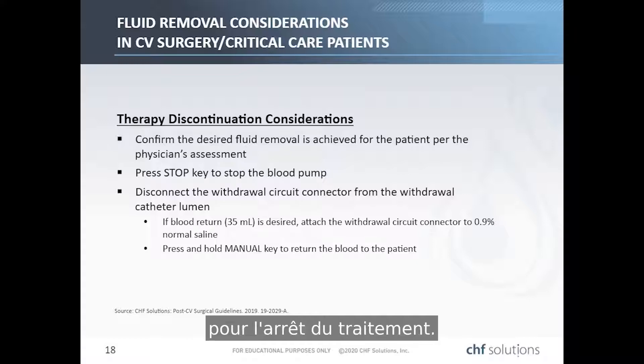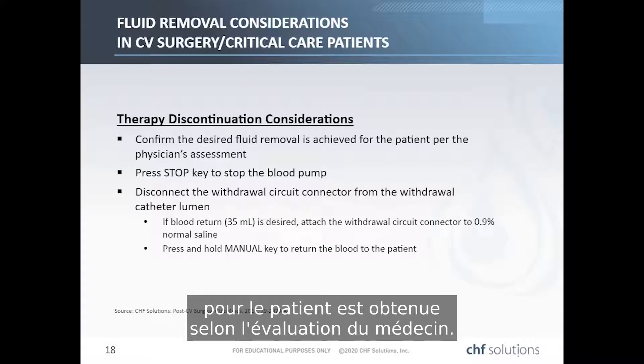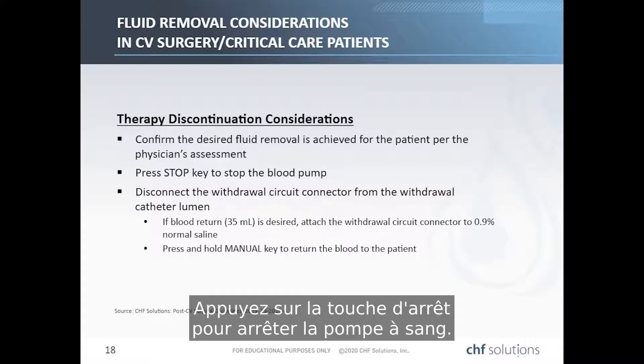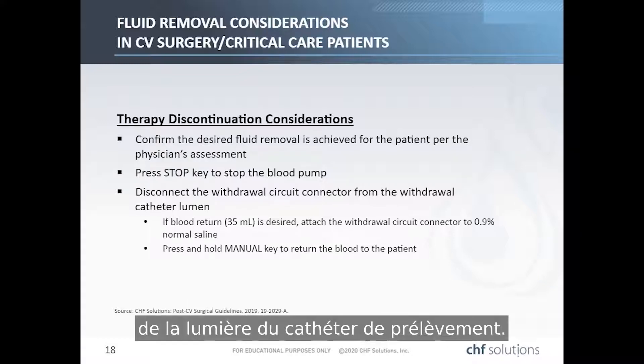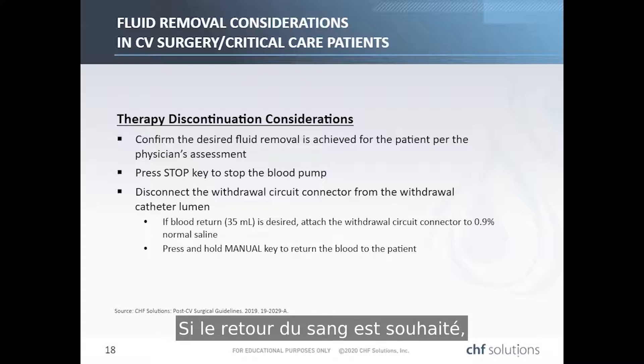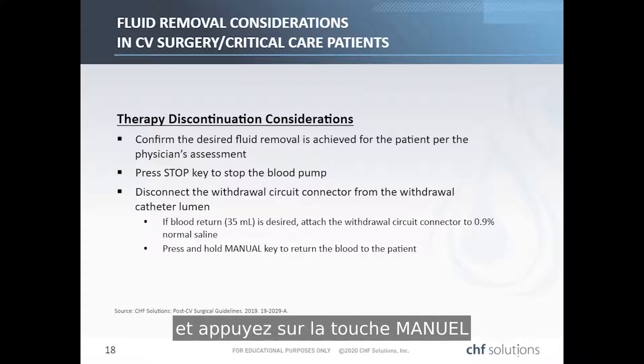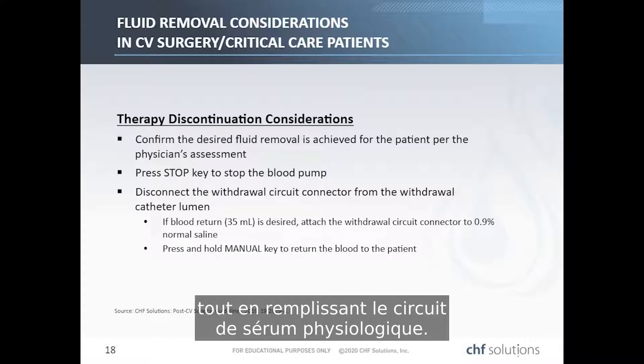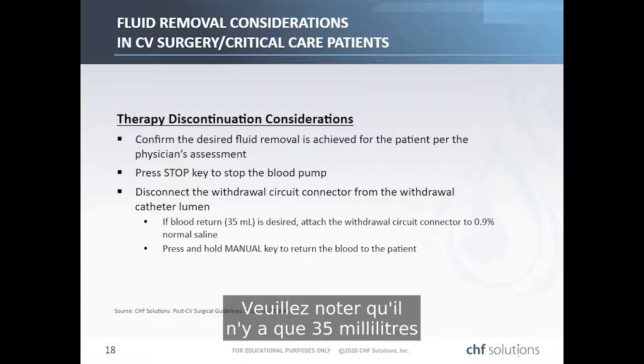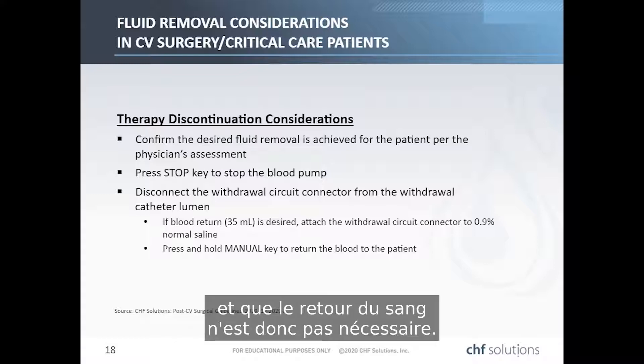For discontinuation of therapy, confirm that the desired fluid removal is achieved per the physician's assessment. Press the stop key to stop the blood pump. Disconnect the withdrawal circuit connector from the withdrawal catheter lumen. If blood return is desired, attach the withdrawal circuit connector to a normal bag of saline and press and hold the manual key to return blood to the patient while filling the circuit with saline. Note that there are only 35 mL in the circuit at any given time, so blood return is not required.